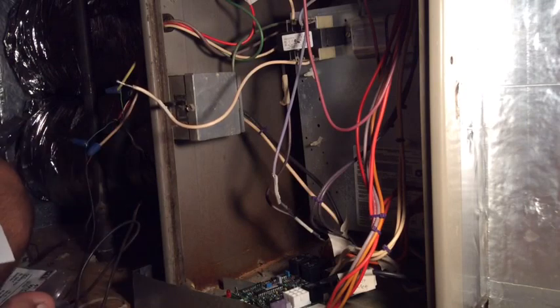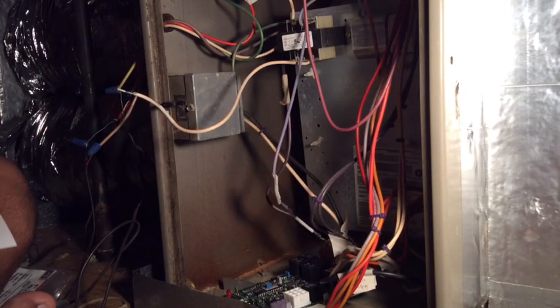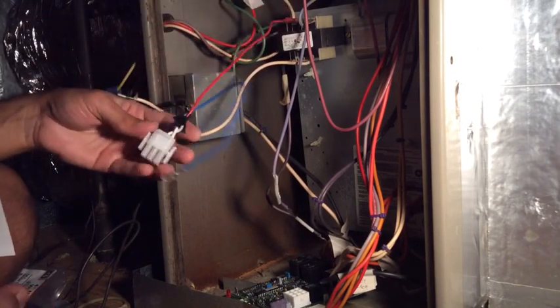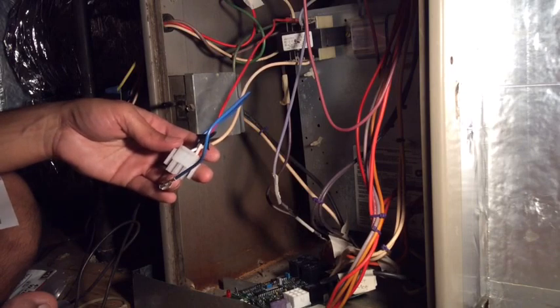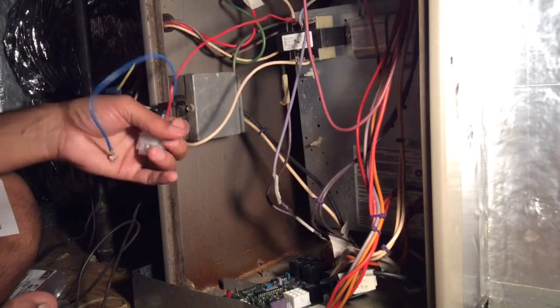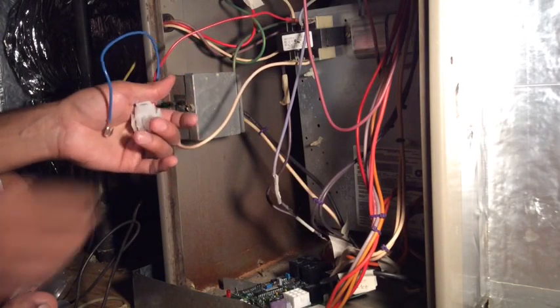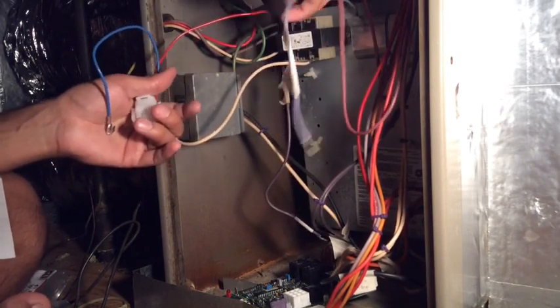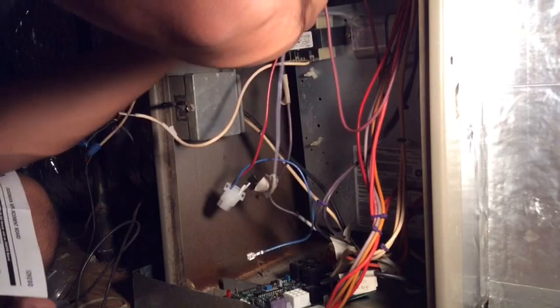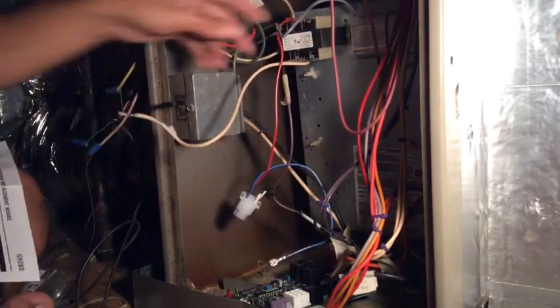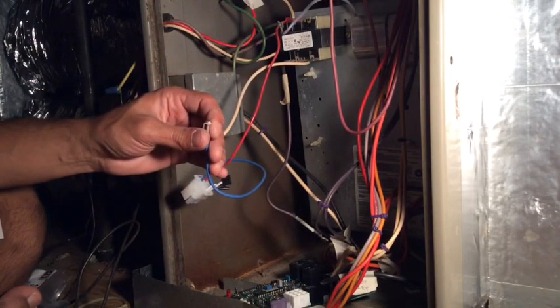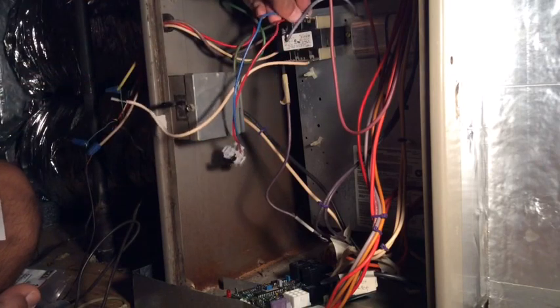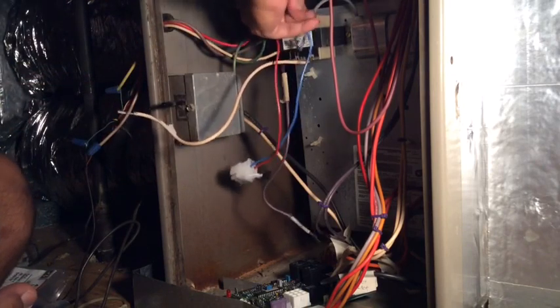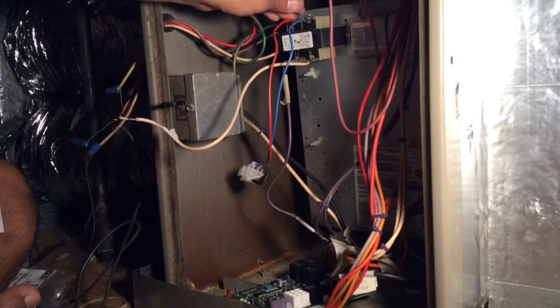Secondary side. Discard. Onto the common terminal, the secondary side of the transformer. Place the blue wire onto the common terminal of the secondary side of the transformer. Place the brown wire onto the common terminal.